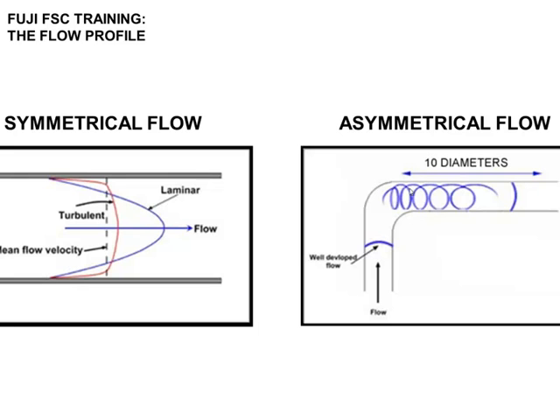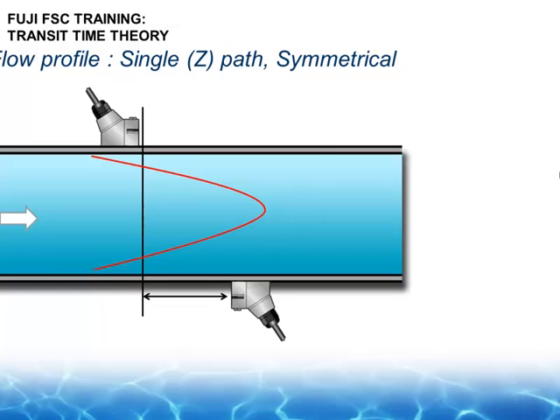If I put my transit time flow meter right here, I'd probably get a fault condition, probably wouldn't get anything at all. But if I went down 10 pipe diameters and put my sensor here, I'd probably have a successful application. So give us your traditional 10 to 15 pipe diameters, and you should be set for most applications. Now, you can get a reading under acute situations, but you're not going to get your overall accuracy statements there.